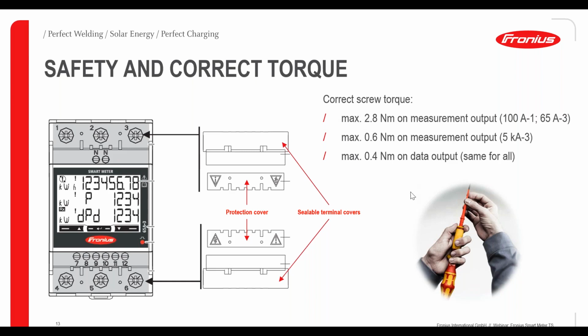For the correct screw torque, we use a maximum 2.8 Newton meter on the measurement output of the first two smart meters, the 100 amps for the single phase and 65 amps for the three-phase network, which means that we are coming to the smart meter from the grid to the pin 1, 2, 3, and we are going from the pin 4, 5, 6 to our loads. And on these connection terminals, we use 2.8 Newton meter. Then when it comes to our commercial smart meter, the 5 kiloamps for the three-phase network, we use the maximum of 0.6 Newton meter. And for the data output, we use 0.4 Newton meter.